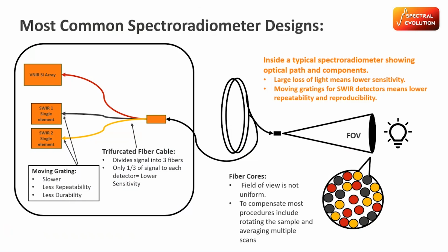So how does a spectrometer work? Older spectrometer designs typically follow this kind of workflow. So you start on the right here with the light bulb. And that's your signal. And your signal is sent through this field of view. So out the end of a fiber, you typically have a 25-degree field of view, which means your field of view is going to be defined by a distance to a target. Now, that signal is sent through a fiber optic cable. And in the older designs, it will go to a trifurcated cable that will bring indiscriminately 1/3 of the signal to each detector. At that detector, you'll have moving gratings that are both slower and less repeatable than our design.